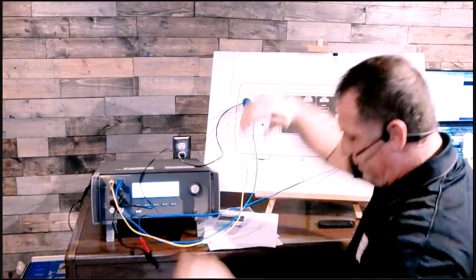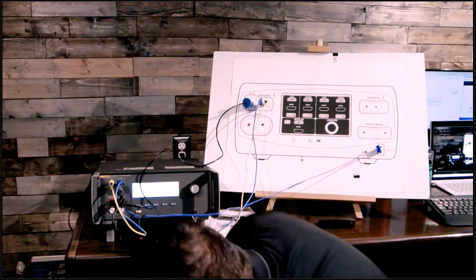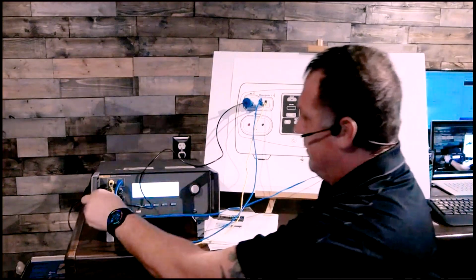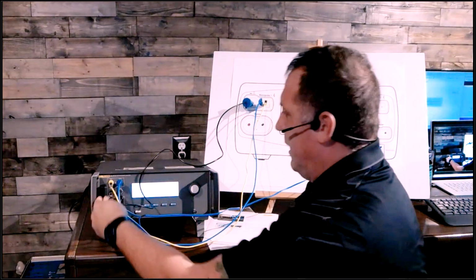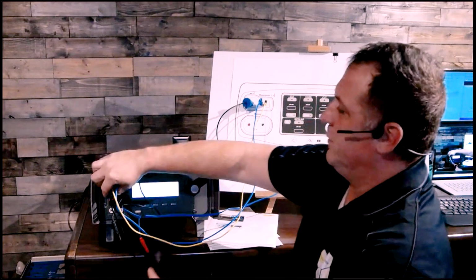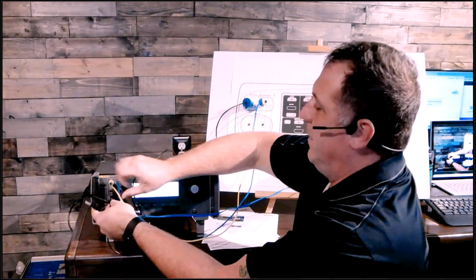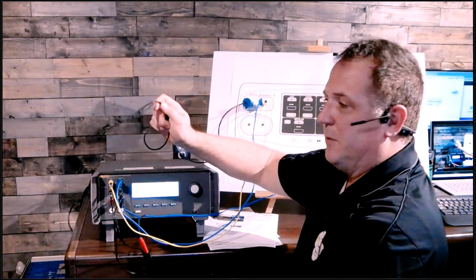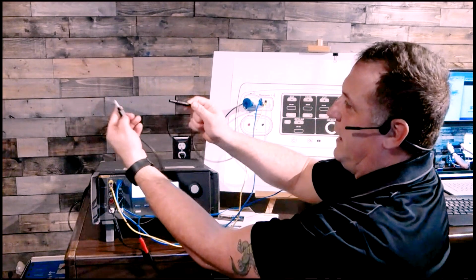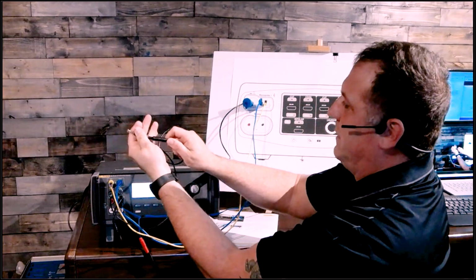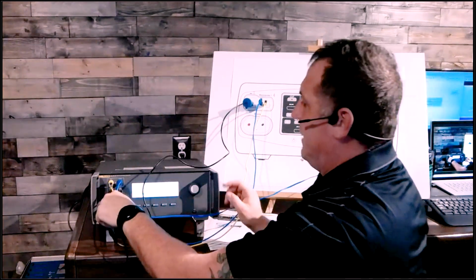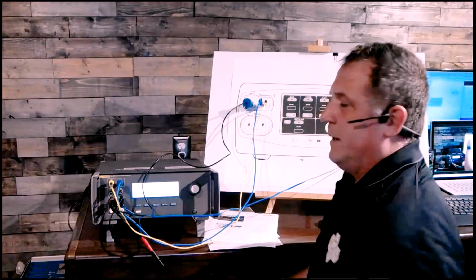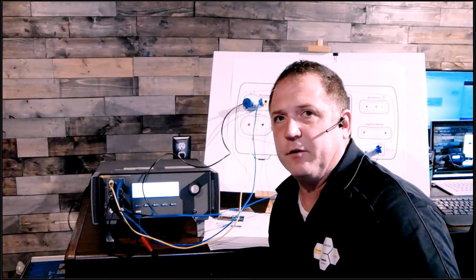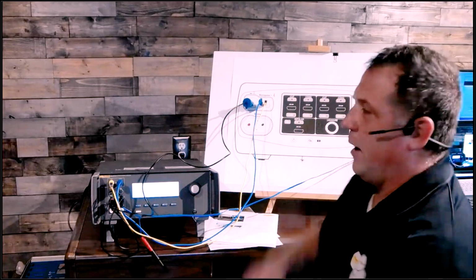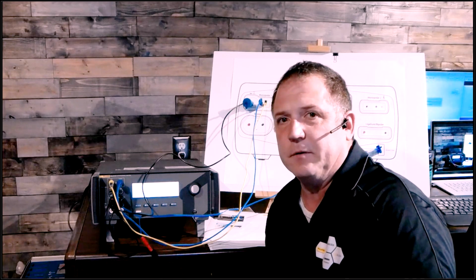I know I put a hole over there — there we go. One more time with my little jumper cable for my common. Uh-oh, there's an issue: there's no jumper on the back of this bipolar activation cable, but there's one on the back of my jumper cable. So I just flip-flop this order, boop, and plug into my variable high. Now I can use that foot switch combination to activate monopolar 1 through the handpiece adapter. Ta-da!